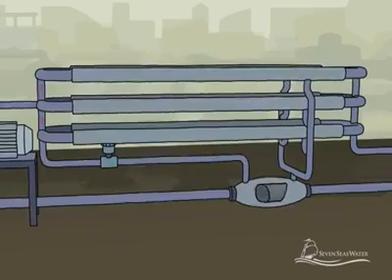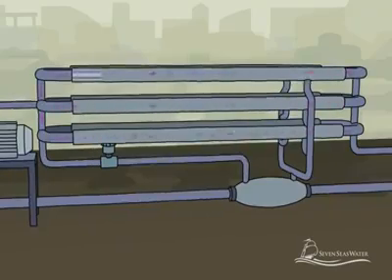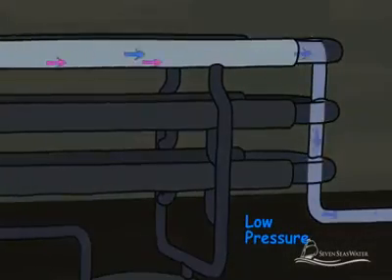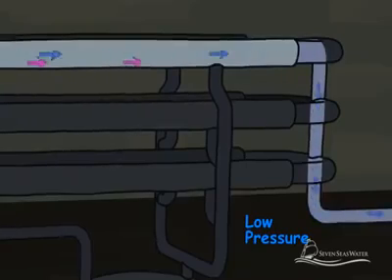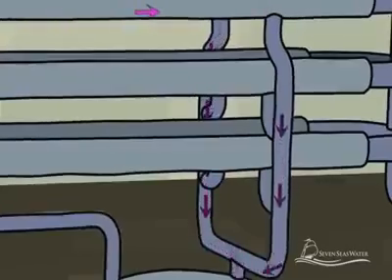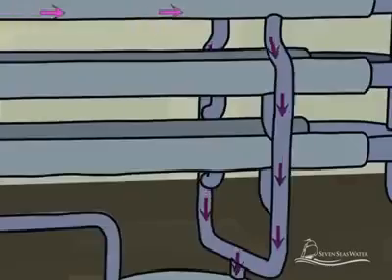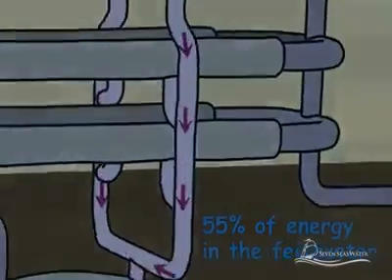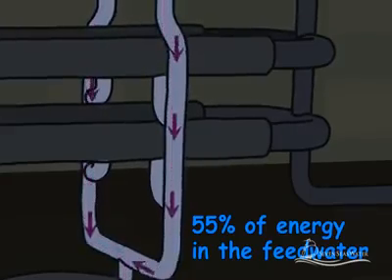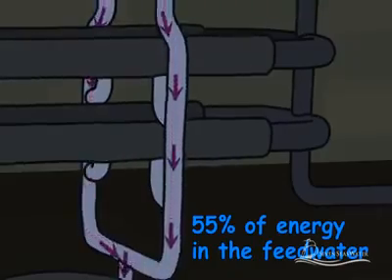As the pressurized seawater enters the pressure vessel and flows across the membrane surface, the water molecules are forced into and through the membrane envelopes, leaving the salt molecules behind. The desalted water passes through the membrane and emerges at low pressure, where it is collected in a tube and directed to one end of the pressure vessel. The concentrated salt stream that is rejected continues to pass across the membrane surface where it is collected separately, retaining about 55% of the total energy of the original seawater stream.